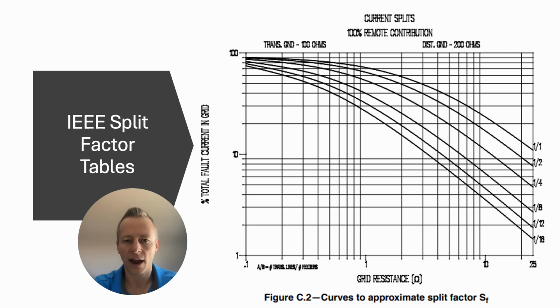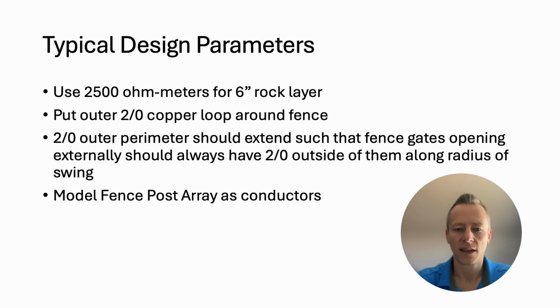And then we only do our grounding study based off the actual grid current and the touch and step potential that it produces. Then just to wrap up this module, some of our typical design parameters for a substation ground grid would be: we like to use 2500 ohm-meters for a 6-inch rock layer. We'll put a 2-aught copper loop around the fence on the outside, and that's per an RUS standard. We also like to have that 2-aught extend out beyond the gate swings. So if you draw it in your CAD drawing, the swing arc of your fence gates, you need to have copper 2-aught out beyond that gate swing.